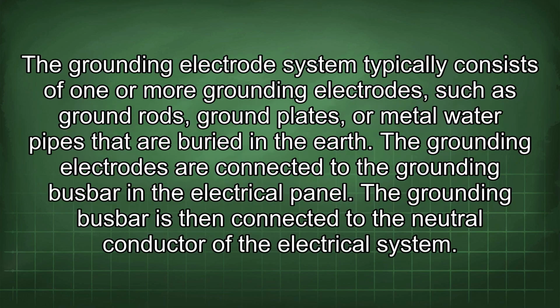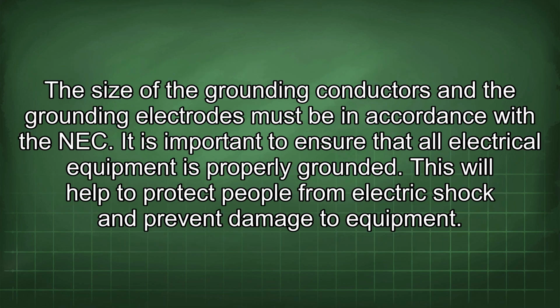The grounding electrode system typically consists of one or more grounding electrodes, such as ground rods, ground plates, or metal water pipes that are buried in the earth. The grounding electrodes are connected to the grounding busbar in the electrical panel. The grounding busbar is then connected to the neutral conductor of the electrical system. The size of the grounding conductors and the grounding electrodes must be in accordance with the NEC.